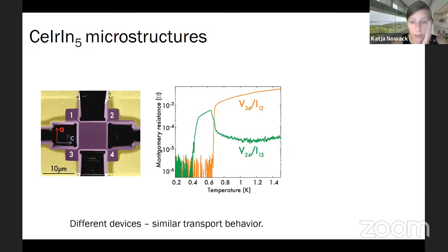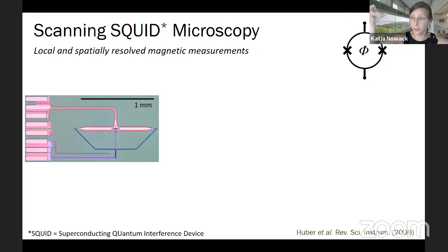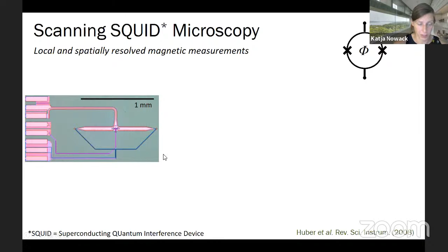And so that is a puzzle, and that's a perfect puzzle to address with a local probe. The local probe that we like to use is a superconducting quantum interference device, or SQUID for short. A SQUID in essence is a superconducting loop interrupted by two Josephson junctions. The SQUIDs that we use are actually really large. They're not just a loop, but really stretched out very wide and have a twist in them. Here you see an optical image of the complete SQUID, and here I'm zooming in on the sensitive area.